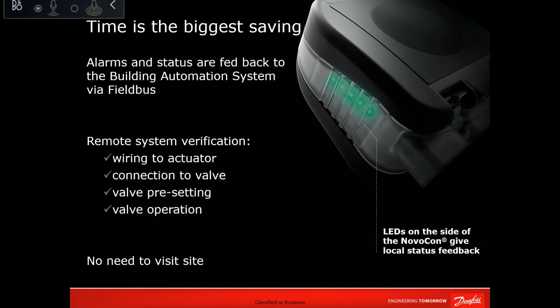Next question. Can we mix Novocon with the standard actuators? If yes, what is the impact? You can mix Novocon with a standard actuator. I mean, Novocon is communicating using BACnet or Modbus communication protocol. So if you are using Novocon, as we said, you can use the local control like a standard normal actuator, or you can use BMS control, or you can use both. But when you use both, you need to tell the BMS to enable both controls.